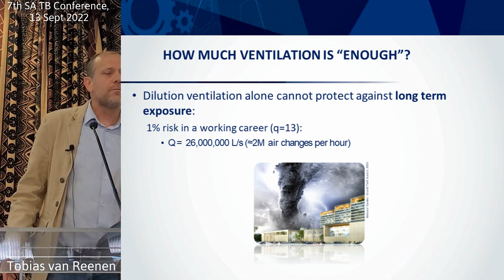For a waiting room, not the tornado scenario, 3,200 liters per second comes out at about 32 liters per second per person, which is a lot more than the 7.5 or 10 that we read in some guidelines. It's a lot of air.